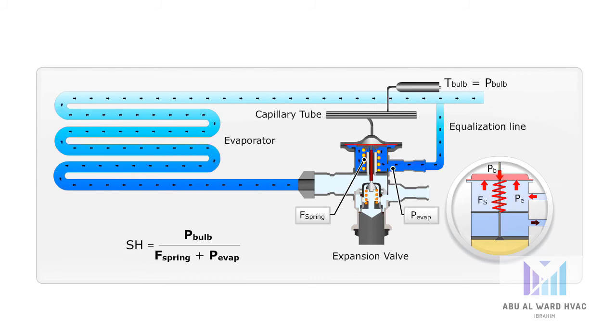If the load in the evaporator increases, the increasing superheat will in turn increase the bulb temperature or pressure. This will open the TXV orifice so more refrigerant is injected.